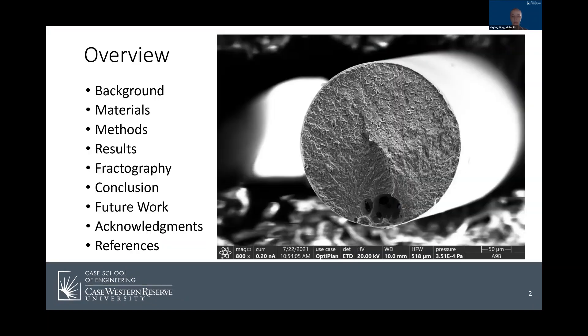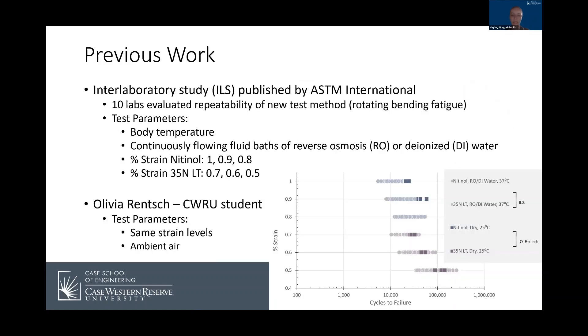Here's a little roadmap of the presentation with the work that led up to my study. An interlaboratory study was published by ASTM International with the goal of assessing the repeatability and reliability of rotating bending fatigue tests. The ILS study consisted of 10 labs assessing the fatigue performance of nitinol and 35N LT in body temperature, continuously flowing baths of either reverse osmosis or deionized water. In addition to the ILS, another student conducted fatigue tests of both materials at the same strain levels in ambient air. These two studies resulted in a large data set that I used as a starting point for my research.